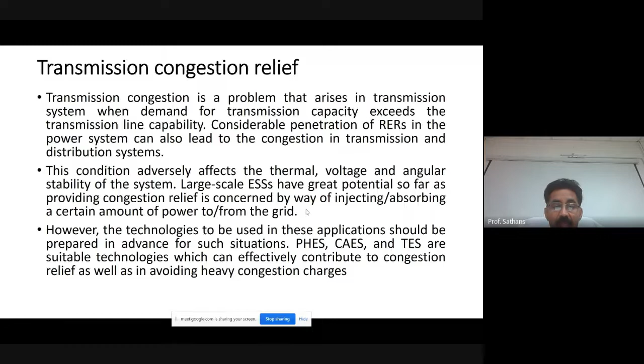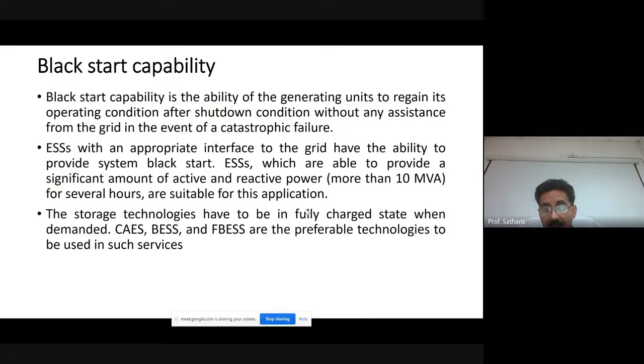Black start capability is the ability of generating units to regain their operating condition after a shutdown without any assistance. If there's been a collapse or blackout, can you restart your generating units without assistance from the grid? For black start capability, ESS can be an appropriate interface to help the system start afresh after a collapse or shutdown. For that, the energy storage system has to be in a fully charged state so it can respond whenever there's a demand.